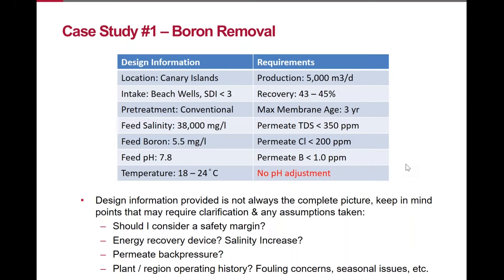Some additional design information: the information provided may not always be the complete picture, so you may need to seek clarification or make assumptions. For example, should you consider a safety margin? When designing a system, exceeding permeate quality requirements typically results in a fine. How much safety margin to use depends on the permeate quality requirements and operating conditions. Another issue: should you consider an energy recovery device, and if it's a pressure exchanger, do you need to account for a salinity increase?